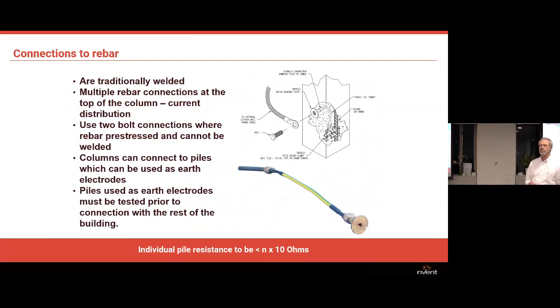Connecting to the rebar, this is showing the Erico product. In New Zealand, we have a product called the Rycon that's made at a factory in Auckland and has been around for decades, so we don't import this other one, because the Rycon factory is also the Erico manufacturer of Erico's Cadweld and so on. But that comprises a steel bar at one end, the top left end of that picture, and that can be welded to your rebar because rebar is difficult to Cadweld to.